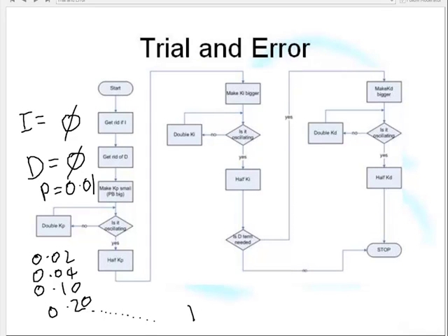Let's say for the sake of argument we've made it 4 and it's oscillating. As soon as we've got it oscillating, you back it off and you make it 2 again. You may actually have to back it off all the way to 0.5 and then bring it back to 2, because once it's got oscillating, it likes to oscillate. So you increase it until it oscillates, and then you back it off. And that's your P term found.